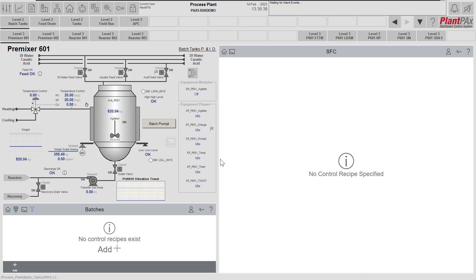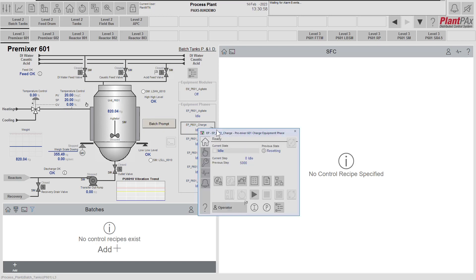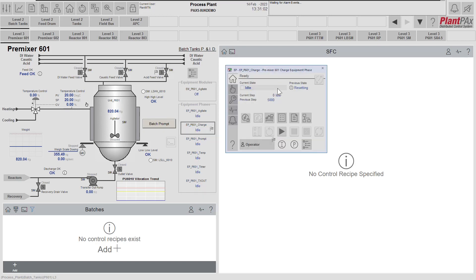In our demonstration we're going to have a look at the charge equipment phase that's been implemented. This controls charging of material into our pre-mixer — we can charge water, caustic, or acid by weight into the pre-mixer. The HMI symbol for the charge equipment phase is shown here, and clicking on this opens up the faceplate. We can see currently that this equipment phase is in the idle state and it is in operator mode, so it can be controlled manually from the HMI. This equipment phase could equally be controlled by a recipe execution system.